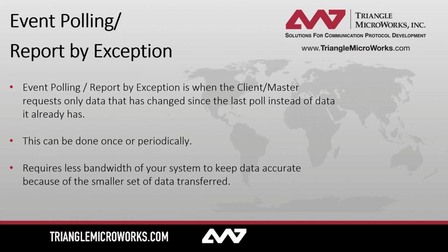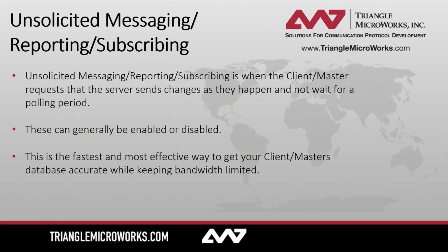Event polling, or report by exception, is when the client or master requests only the data that's changed since the last poll, instead of all the data that it already has. This can be done once or periodically as well. This requires less bandwidth of your system to keep data accurate because of the smaller set of data that is being transferred. The last one we'll be looking at today is unsolicited messaging, reporting, and subscribing. This is when the client or master requests that the server sends changes as they happen and not wait for any sort of polling period. These can generally be enabled or disabled. This is the fastest and most effective way to keep your client or master's database accurate while limiting bandwidth.